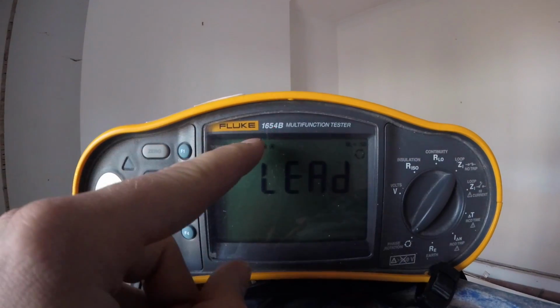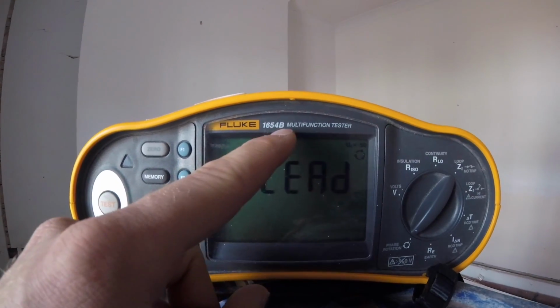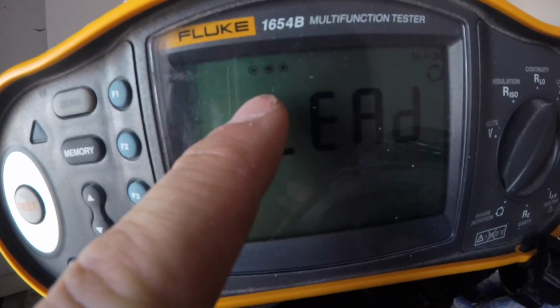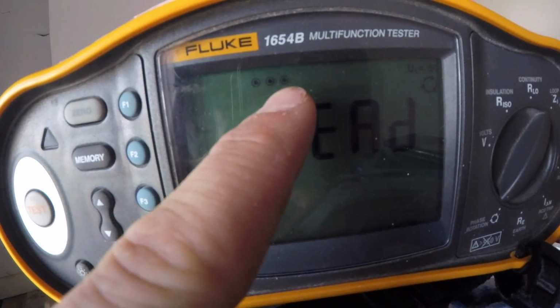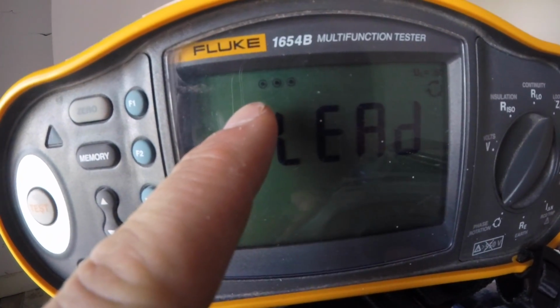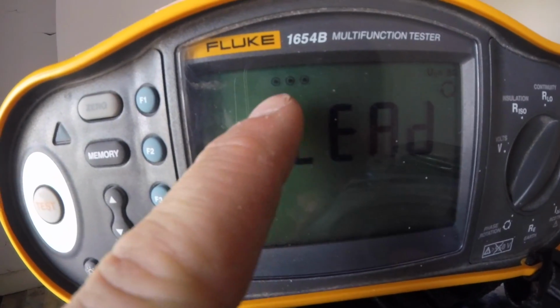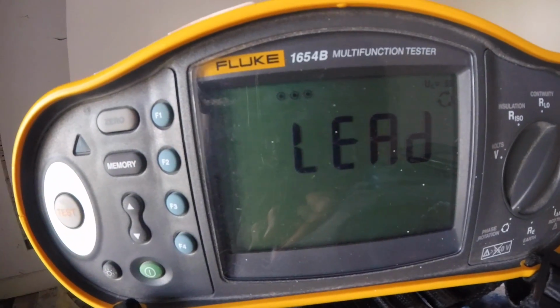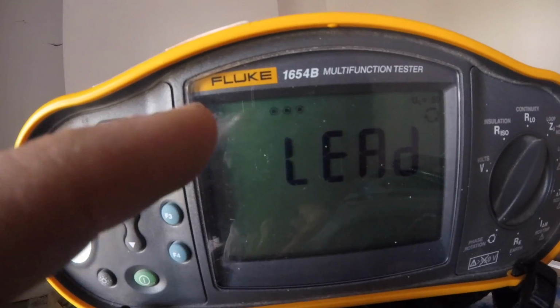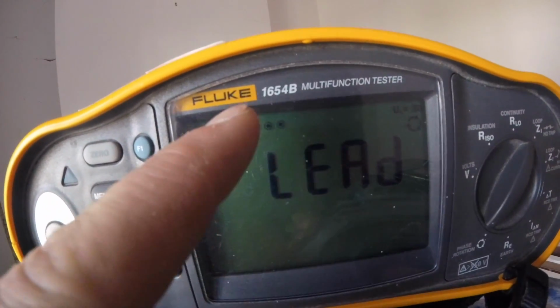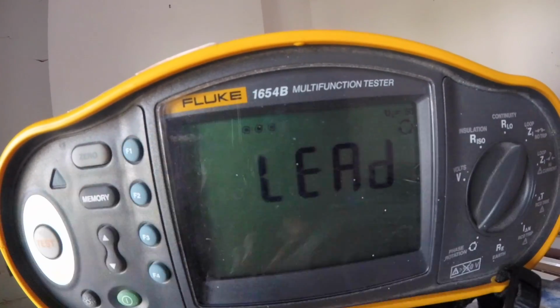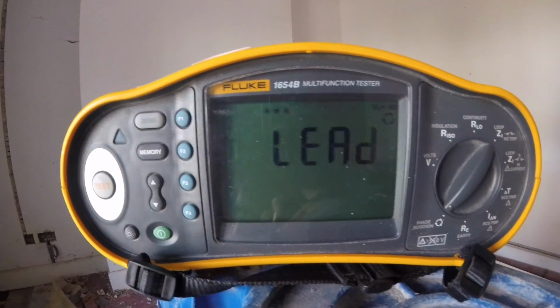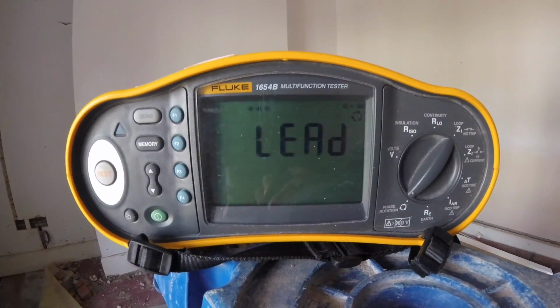So if there is incorrect polarity, it will come up with a couple of little arrows on there just to show the probes you've got plugged in on what they should be, basically. So say you've got your neutral on the earth, it will let you know on there. Say you've got your live on the earth, it will let you know on there by a couple of different arrows. So this machine does actually prove polarity as well.